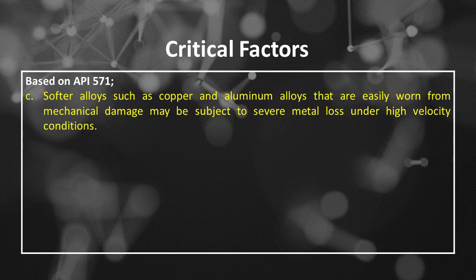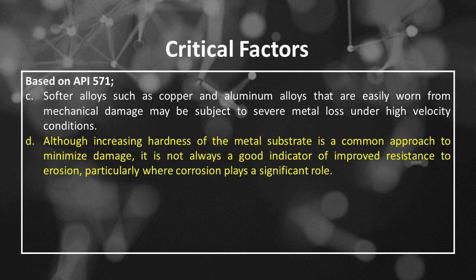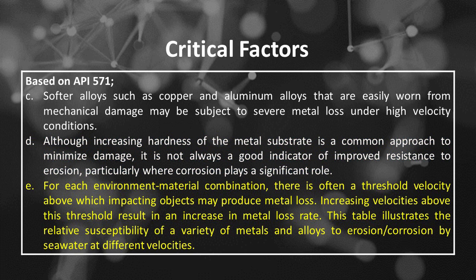The third is softer alloys such as copper and aluminum alloys that are easily worn from mechanical damage may be subject to severe metal loss under high-velocity conditions. The fourth is although increasing hardness of the metal substrate is a common approach to minimize damage, it is not always a good indicator of improved resistance to erosion, particularly where corrosion plays a significant role. The fifth is for each environment material combination, there is often a threshold velocity above which impacting objects may produce metal loss. Increasing velocities above this threshold result in an increase in metal loss rate.